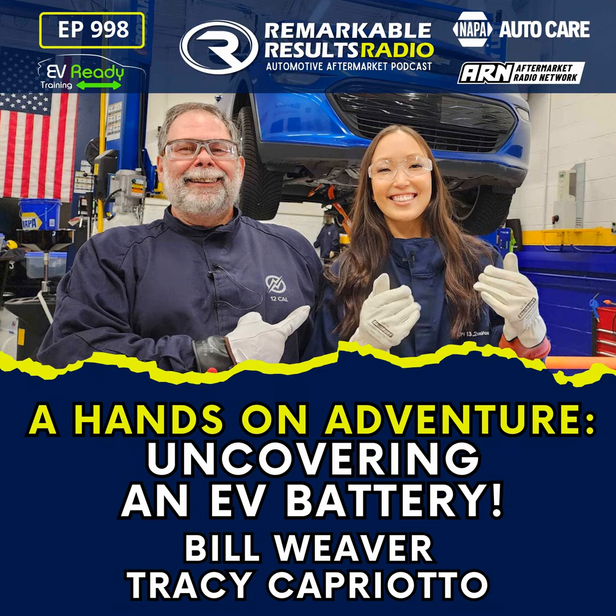Our fourth test connection is going to take this pack in right here, insulated screwdriver by the way. There's just a small tab we have to release to pull up, and we can get to number 4 there. Now you see we got up to 156 volts on that one, and then our final test is going to be right here before we go into that manual service disconnect, and that should get us to 188 volts. Yep.